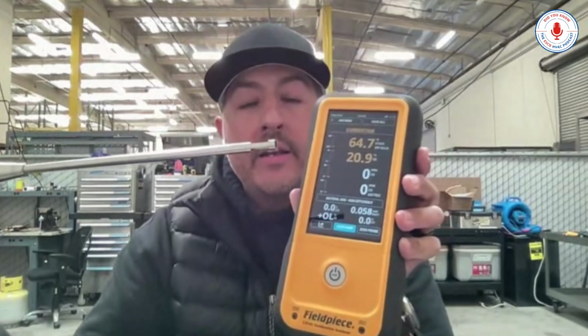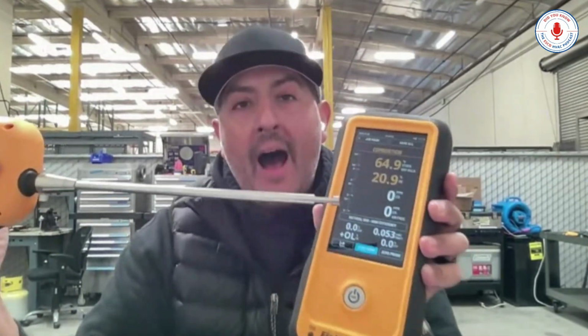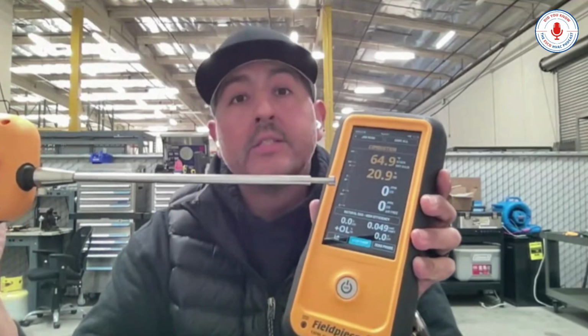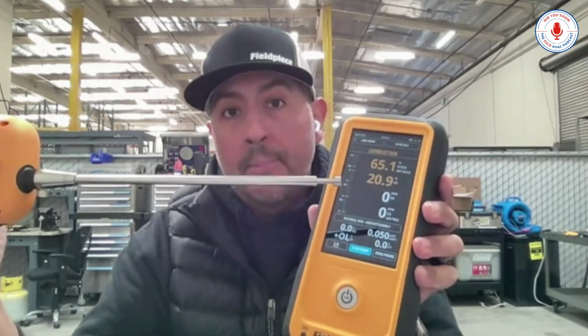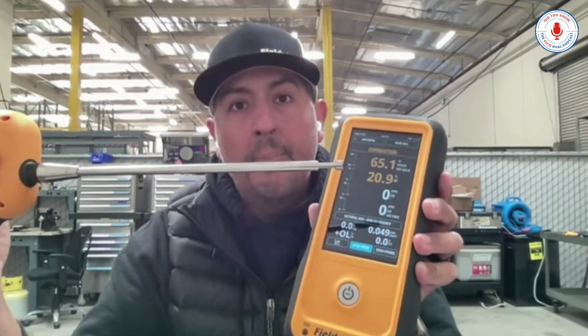Now, as we know, in the flue of a high efficiency furnace, we have the presence of water, right? That's just how those appliances work. That's what makes them more efficient than other appliances. And as you know, or maybe you don't know, the sensors within a combustion analyzer are not very fond of getting wet. They don't want the moisture or the water vapor. So your typical combustion analyzer is going to have something like a water trap somewhere between where you're sampling the gas and the sensors of your tool. Absolutely. The purpose of that water trap is to take the water vapor, condense it, and hold it for you so that it does not pass through to the sensors.